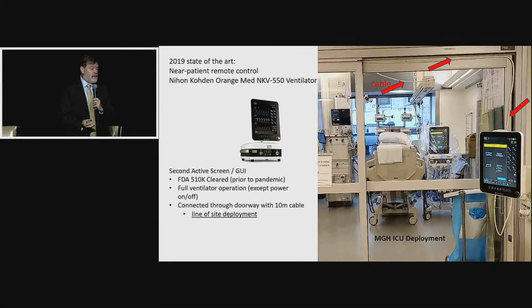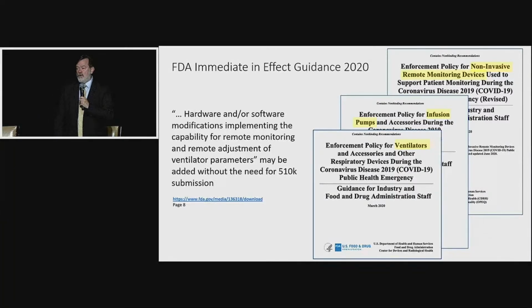Think about what you would change on a ventilator if you can't see the patient. Some things maybe, but maybe not everything. And we'll talk a little bit more about that. The other very important development is that the FDA, in the spring of 2020, released 3 immediately-in-effect guidance documents, all of them for remote control. These documents permitted manufacturers to add remote control to already cleared devices, devices that were already being marketed: ventilators, infusion pumps, and monitors. This provided a pathway for rapid innovation, and was almost certainly based upon the experience with Ebola and the years of comfort that was obtained with the concept of remote control.